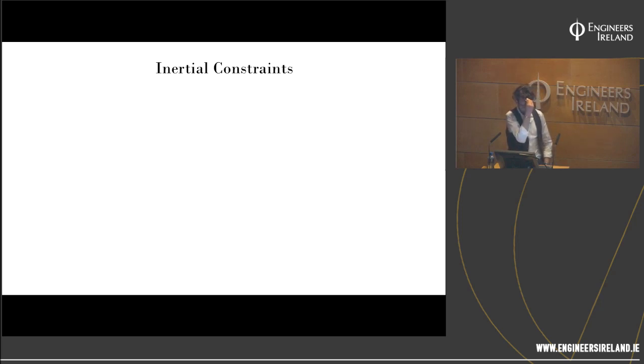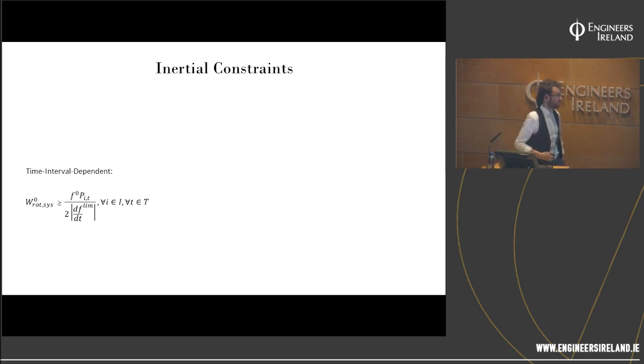So we've devised an inertial constraint within unit commitment. Quick peek of it there. I don't want you to get too worried about it. All you do is you define your rate of change of frequency that you're worried about. What the constraint does is it'll modulate, or dynamically change, the inertia of the grid to meet whatever requirement you set.